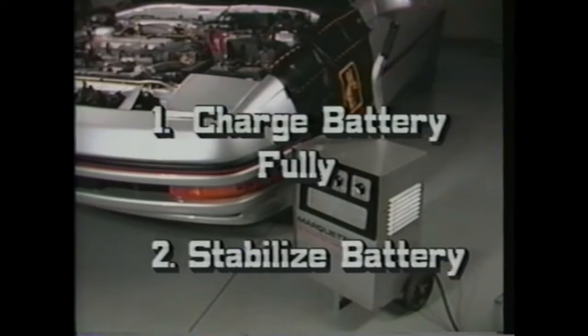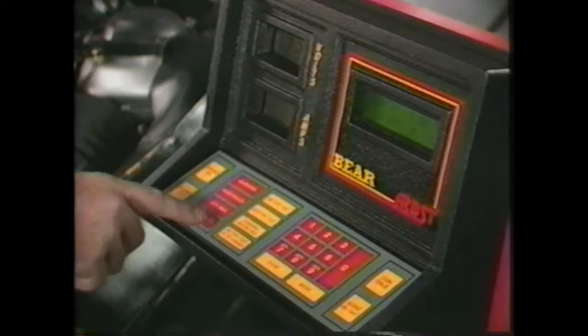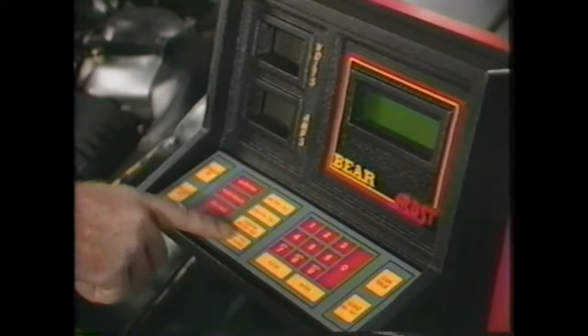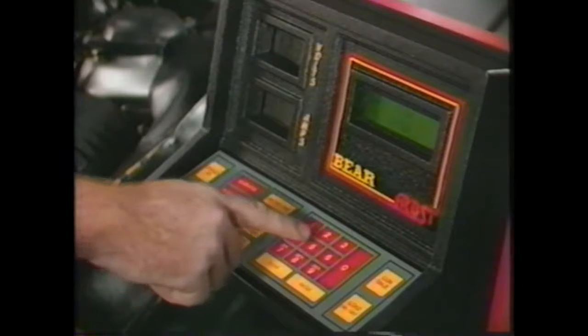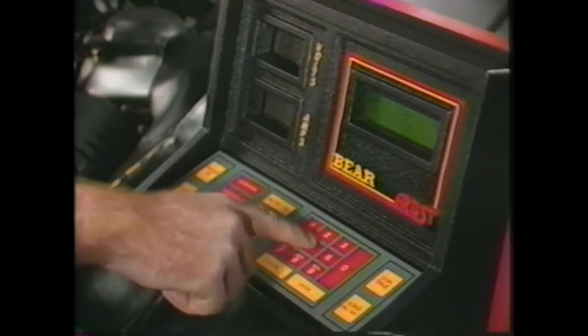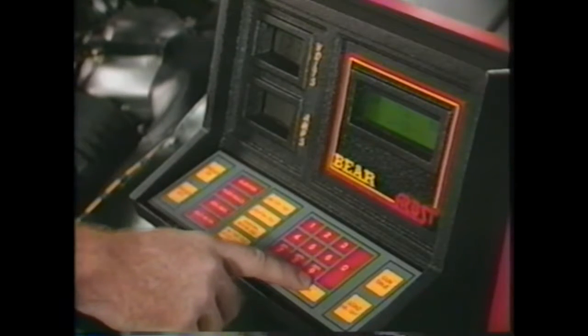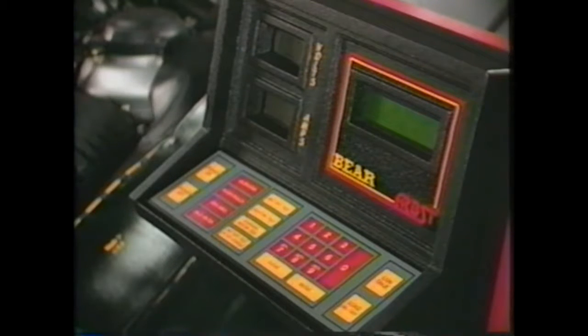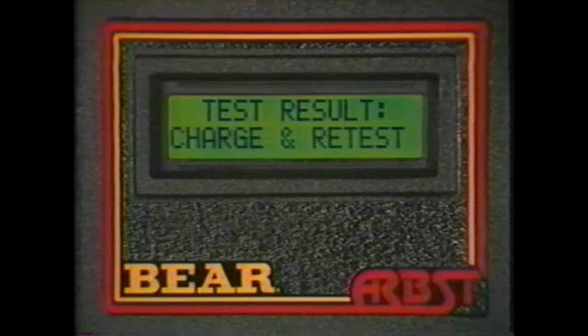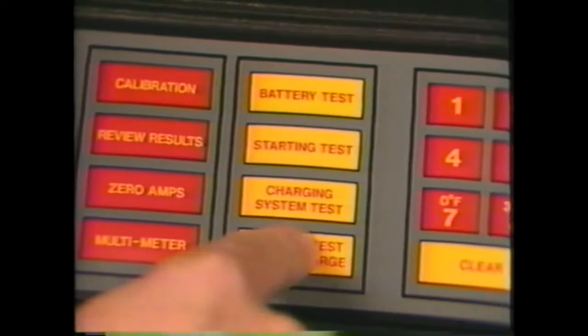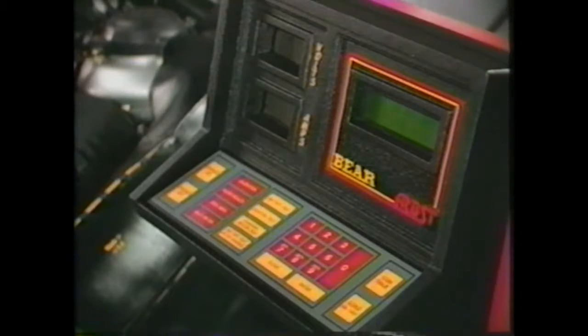After the battery is fully charged and stabilized, test it again, this time using the battery test after charge. This battery test after charge is similar to the battery test we just ran. In fact, the procedure is exactly the same. However, the results are calculated differently. The tester takes into account that the battery has been fully charged when it calculates the results. For this reason, the battery test after charge must be run only on batteries that have been fully charged.